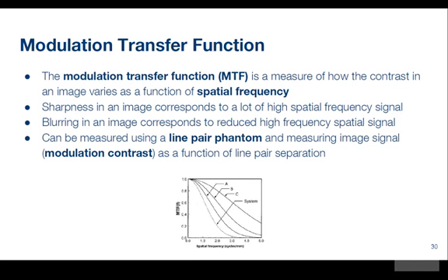And the other thing to remember is that our imaging system is made up of a whole chain of separate contributions. So the individual components might have very good modulation transfer. This component C here is transferring high frequency information very well, but overall the system is going to be worse than that, because these other components are not transferring the high frequency information as well. So the overall system modulation transfer function is always going to be worse, if you like, than the individual components.